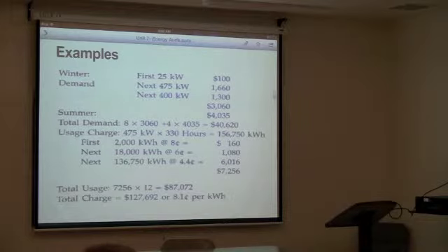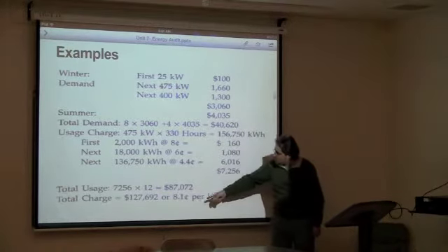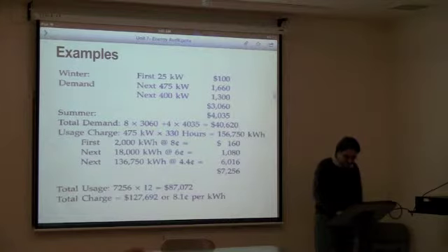When you're trying to build a factory, when you go buy a motor, and you say, okay, this motor is 100 kilowatt, this is what I'm going to pay, this is the amount of energy, you got to multiply by 1.5 to calculate it roughly, because there is a demand, and demand charges are very important, as you can see here. 1/3 of the total charge is going to be coming from the demand.